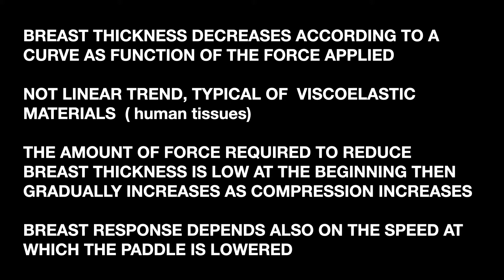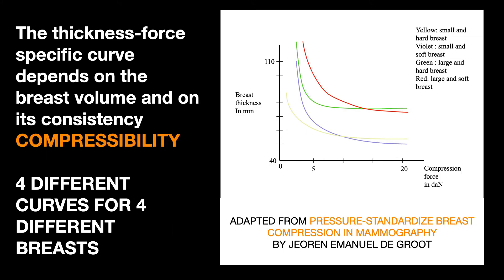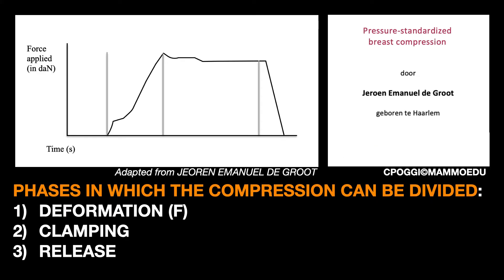The response in decreasing thickness with respect to the force exerted also depends on the speed at which the compression paddle is lowered. The thickness-force-specific curve depends on the breast volume and its consistency — what in the first lesson we called breast compliance or compressibility. You can see here a qualitative graph demonstrating four different responses by four different types of breasts, adapted from a very interesting work by the Dutch colleague de Groot. The compression process can be divided into three phases, again according to de Groot. First, deformation, in which the breast gradually decreases in thickness as the compression paddle lowers and is flattened onto the detector surface, measured in force.